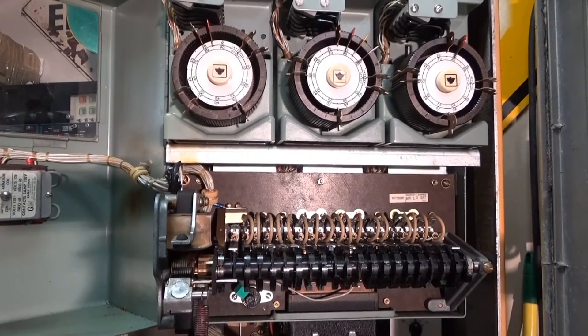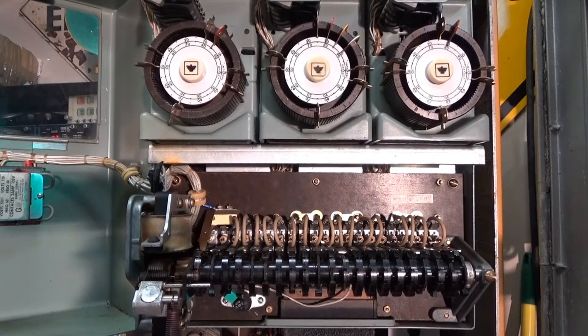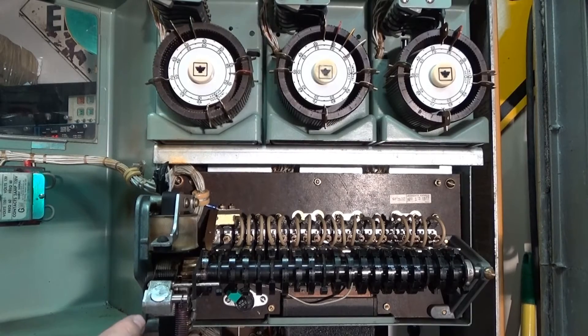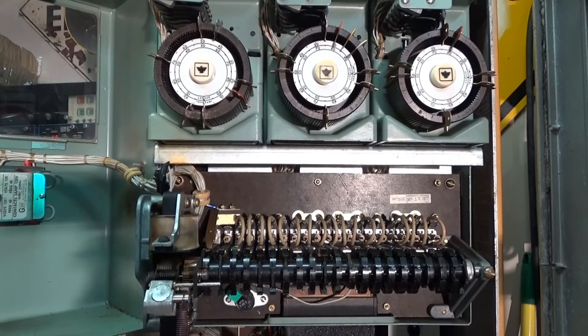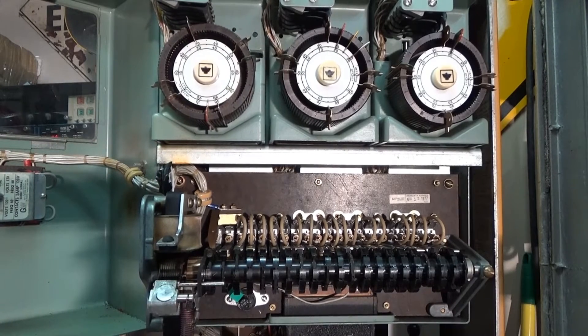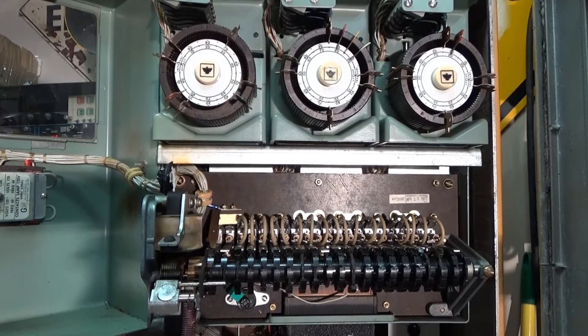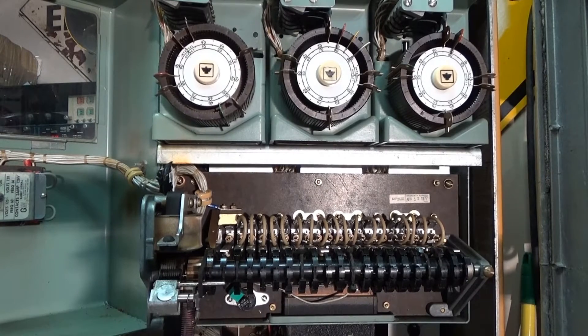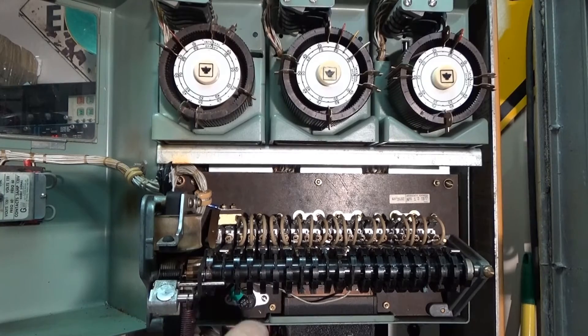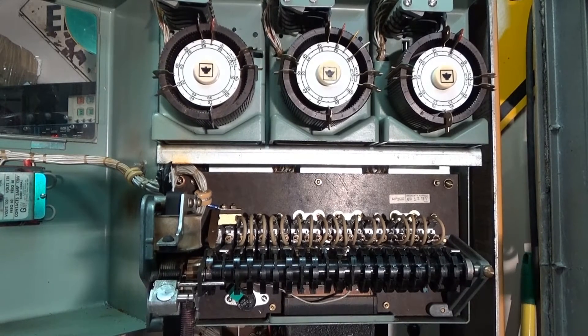As you can see, the cams and contacts are located under the dials, making them conveniently accessible from the front. When the dial comes around and touches a contact, it engages this plunger and magnet, causing it to go up and down and advance the cams one position. What you would do is break out the cams for the sequence of lights you want on and off, using a chart to mark off the different places to break out a piece of the cam. You can see the little contacts for the green, yellow, and red lights — as they drop they make contact, and as they raise they break contact.